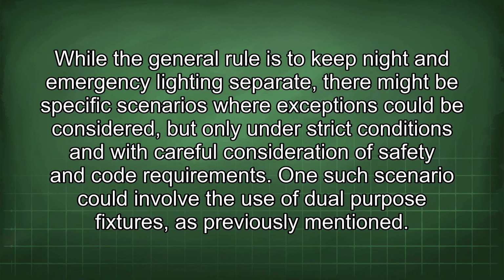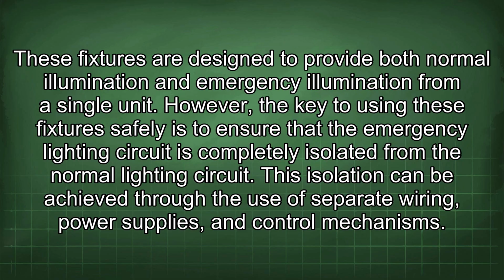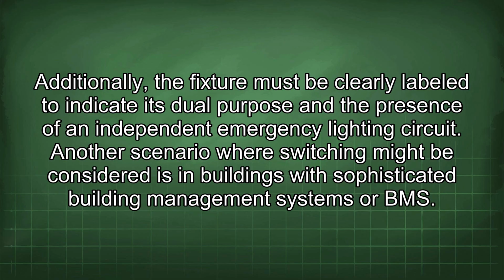While the general rule is to keep night and emergency lighting separate, there might be specific scenarios where exceptions could be considered, but only under strict conditions and with careful consideration of safety and code requirements. One such scenario could involve the use of dual-purpose fixtures, as previously mentioned. These fixtures are designed to provide both normal illumination and emergency illumination from a single unit. However, the key to using these fixtures safely is to ensure that the emergency lighting circuit is completely isolated from the normal lighting circuit. This isolation can be achieved through the use of separate wiring, power supplies, and control mechanisms. Additionally, the fixture must be clearly labeled to indicate its dual purpose and the presence of an independent emergency lighting circuit.